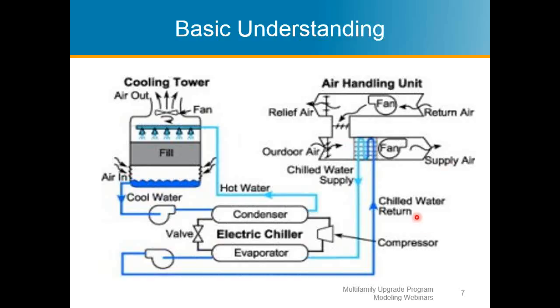Okay, great. So we have the cold water coming off of the evaporator side. That's going to your indoor air handler. You have return air and outside air being mixed in a mixing box or return plenum, kind of thing you may see in a multifamily scenario, running over the cooling coils, cooling that air down and pulling the hot air out. This is then warmed up and taken back through the cycle where it goes to the condensing loop. It takes that hot water out to your cooling tower, where it's cooled down and sent back through. So I'll get more involved in it, but this is a simple, basic understanding. I'm trying to show you the comparison between this and what you may be used to seeing with your split DX kind of systems.